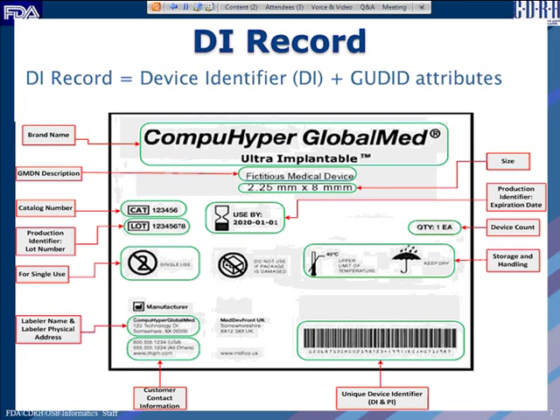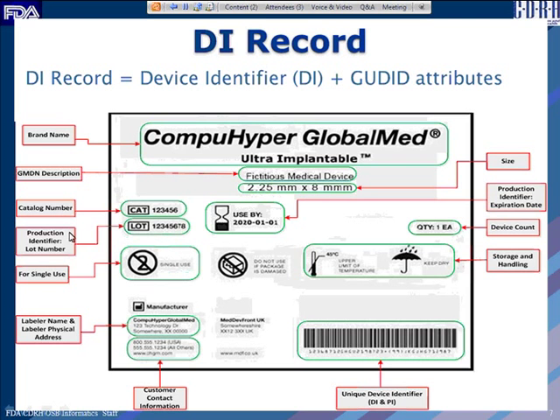A Device Identifier record is basically the device identifier, which is the primary key, plus the other attributes collected in GUDID. Most GUDID attributes come directly off the label or labeling of the device — for example, the brand name, GMDN description, catalog number, and production identifier lot number. For lot number, GUDID stores yes or no indicating whether it is on the label. Additional attributes include single use, the labeler name, physical address, and contact information for customers.